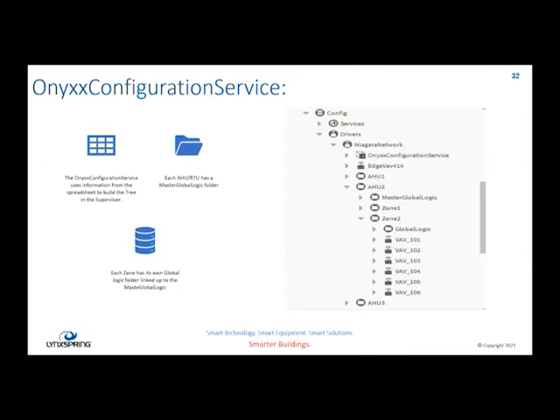The Onyx configuration service, the rapid integration tool, will go in there and build your tree for you. Inside your spreadsheet, you told it, we have air handler 1, air handler 2, rooftop unit 1. We have zones inside each one of those air handlers or rooftop units. So you have zone 1, 2, 3, or first floor east, first floor west. However you break those zones up, it doesn't care. Then underneath those, it puts the appropriate VAV in there. So we build the tree for you, and those graphics are in there. All of your global logic is in there. Your air handler has a master global logic folder that is pushed down to the zone global logic. The zone global logic pushes its information down into the VAV itself.